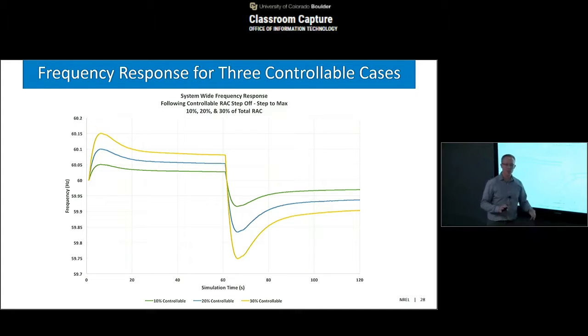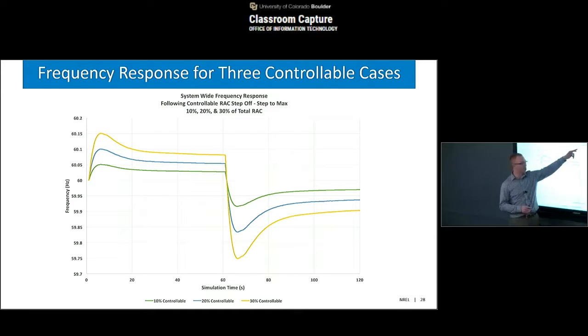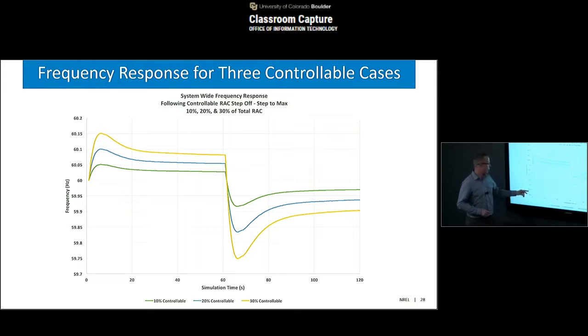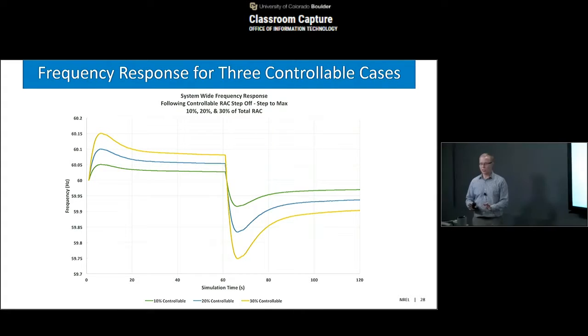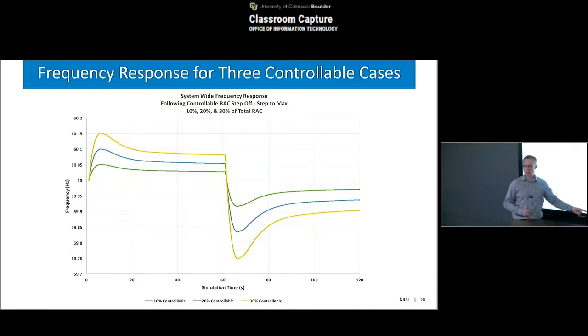In frequency studies, you look at the nadir, and then how fast the system responds and settles. If you had that 30% load, you'd drop below 59.8 Hz and start shedding load because of that. Remember, this is without a lot of wind and solar in the system. If you added more wind and solar, this would go even deeper given how we currently operate the system.